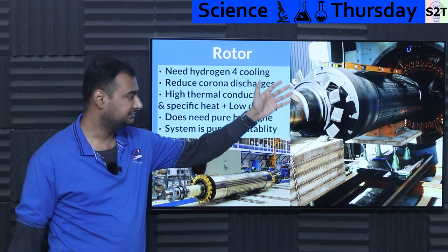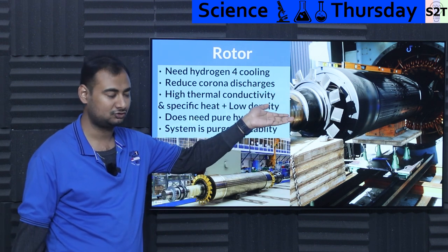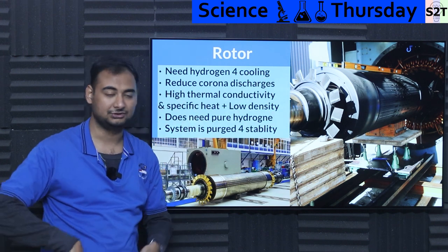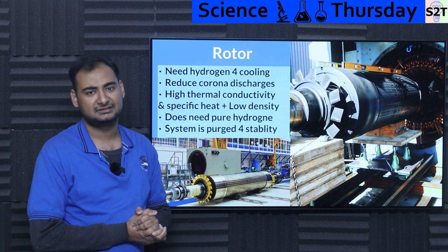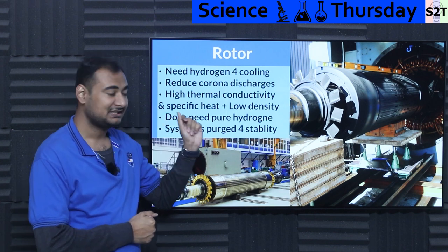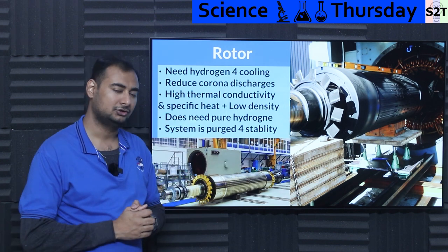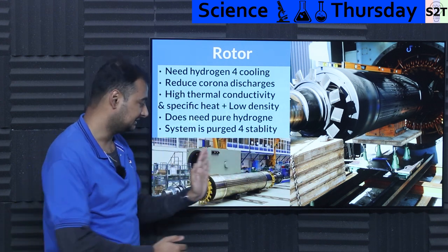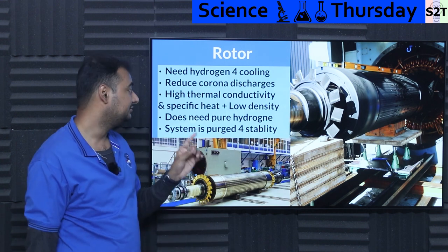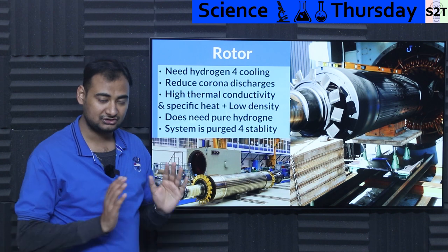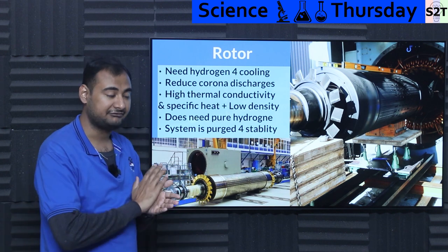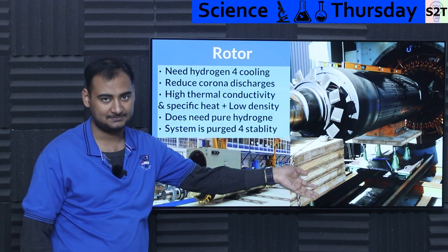When you're talking about something this big, you can't run 220 volts — amps would become unmanageable. So they try to make the voltage as high as possible, though voltage is generally limited to under 30 kV. These generators run on kV scale, so they have corona discharge. Oxygen plus corona discharge is not a good combination. But if you evacuate the generator chamber and flush it with hydrogen, you reduce corona discharge to a level where the lifespan of the dielectric insulation is much, much higher.